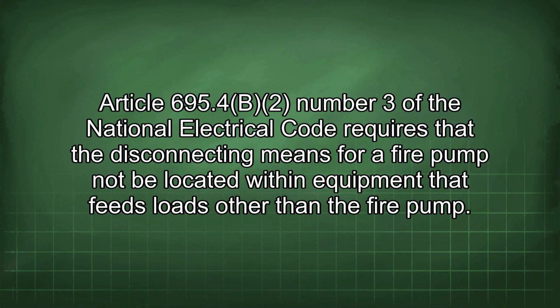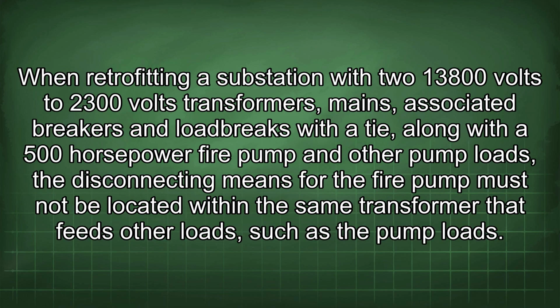Article 695.4 B2 Number 3 of the National Electrical Code requires that the disconnecting means for a fire pump not be located within equipment that feeds loads other than the fire pump. When retrofitting a substation with two 13,800 volts to 2300 volts transformers, mains, associated breakers and load breaks with a tie, along with a 500 horsepower fire pump and other pump loads, the disconnecting means for the fire pump must not be located within the same transformer that feeds other loads, such as the pump loads.